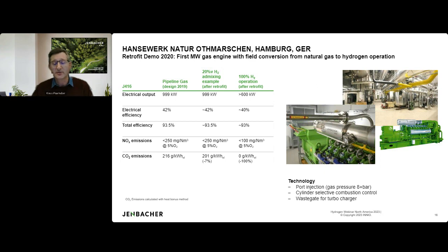What was very interesting to see, and from our side expected, was lower NOx emissions when running on 100% hydrogen. We could reduce NOx from 250 milligram per cubic meter to less than 100 milligram when operating on 100% hydrogen.